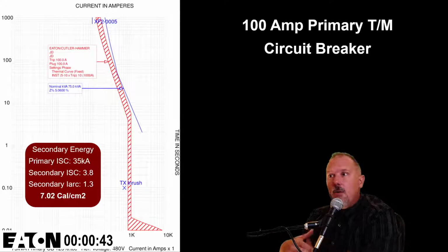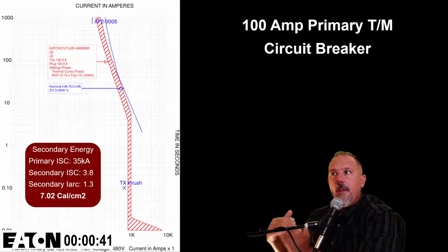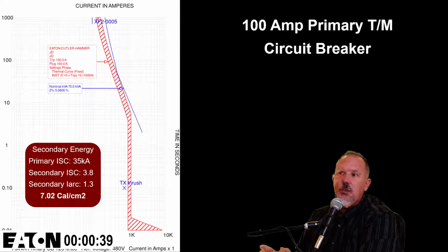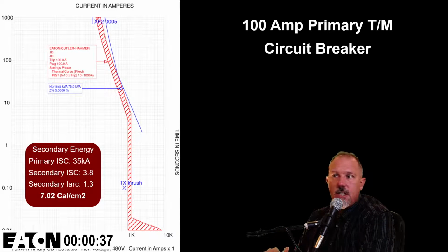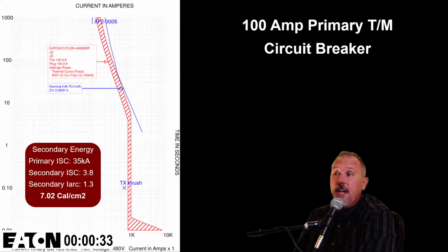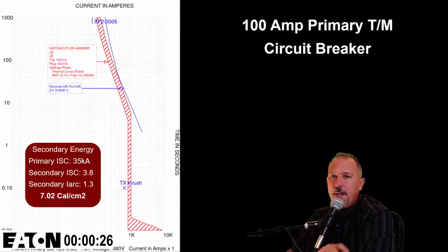Now, I lowered the overcurrent device on that primary down to 100 amps. And look, it squeezes by. I had to get an adjustable instantaneous. Other 100 amp and even 110 amp breakers had a very hard time with that inrush current. Now, if I did 8 times inrush, I would probably have a little bit easier of a time. But again, some breakers at 100 amps or even 110 amps are really pushing it close.